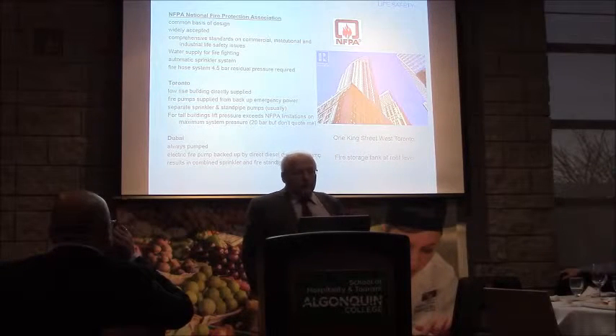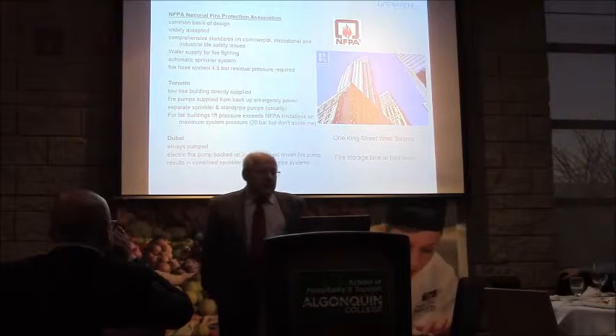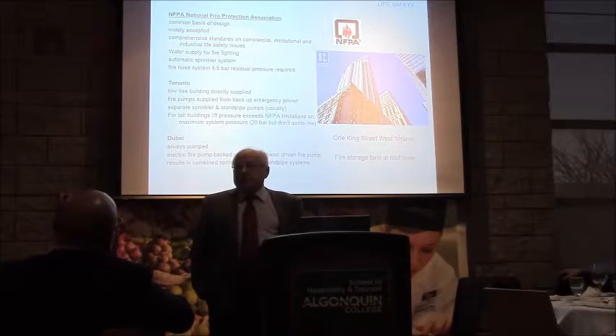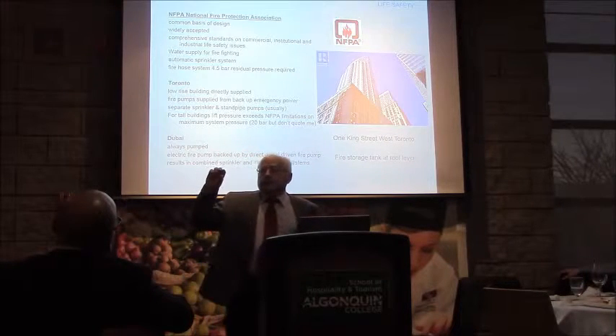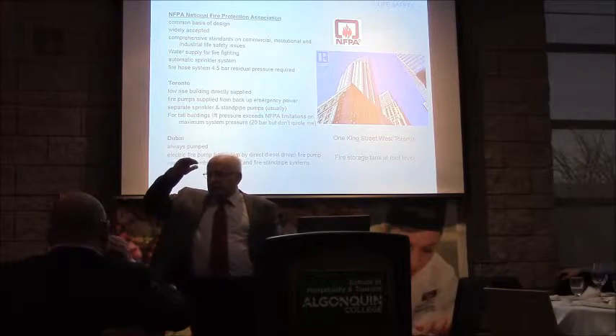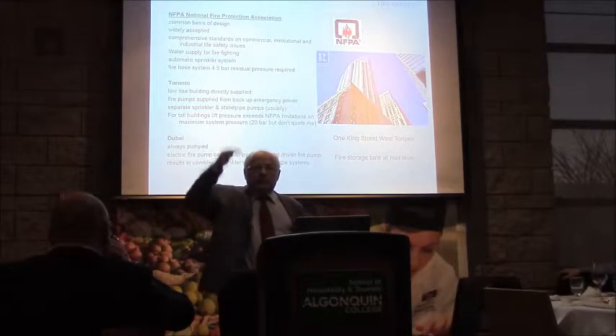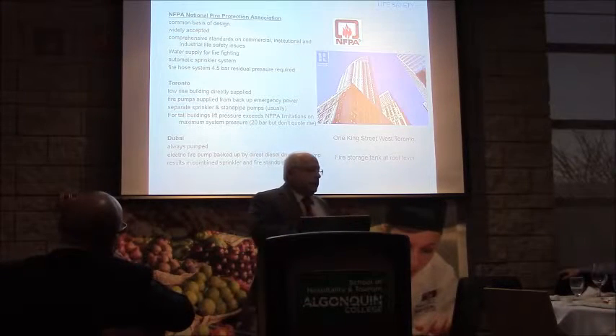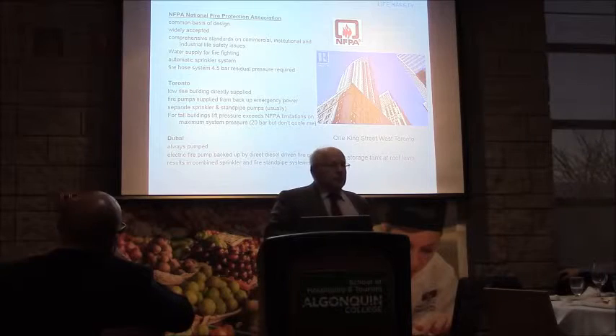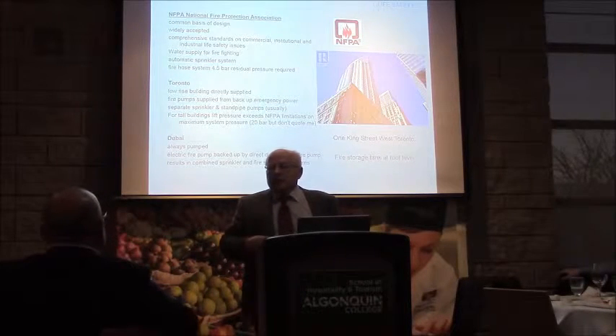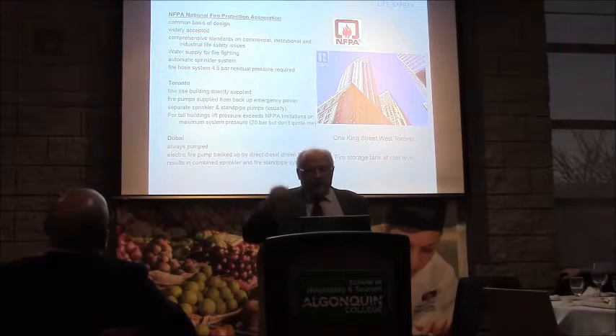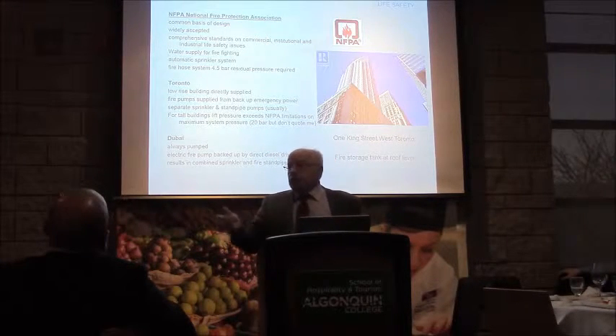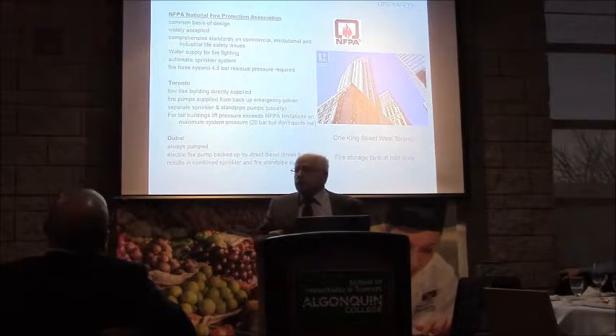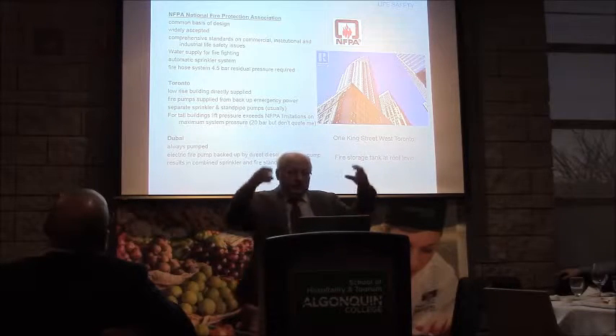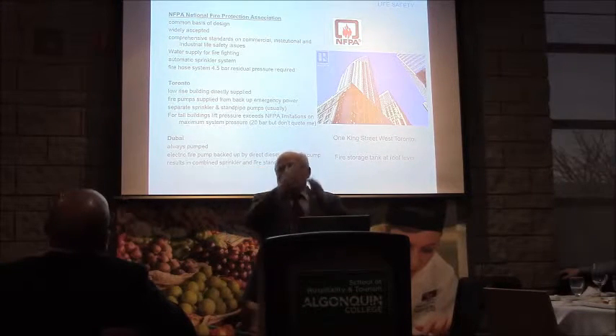Now at 1 King Street West in Toronto, a project that I was a contractor on back in a previous life, we had fire storage tanks at the roof level, and we just made it before the limit, something like 296 PSI lift that you can have before NFPA says no more. So the fire pumps in the basement, there are large turbine pumps reaching down into a collection tank system, and we were able to lift it up into the tanks on the roof level, which on this very slender building, if you've ever seen 1 King Street, it was built on top of an old heritage building, very, very slender, and I'm sure that tank is helping it in its vibrations.